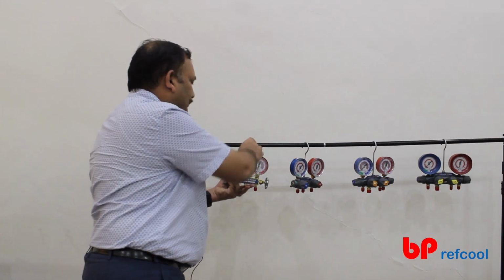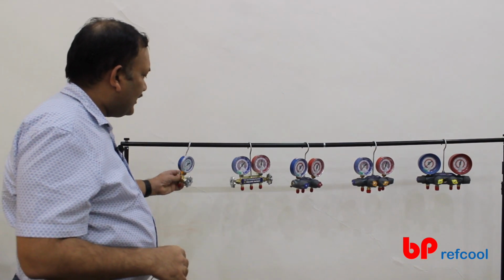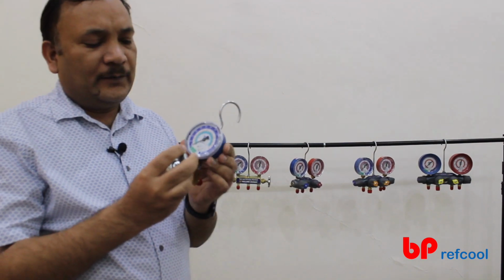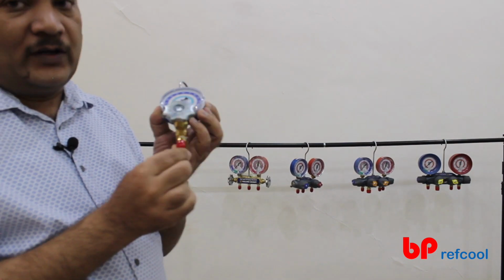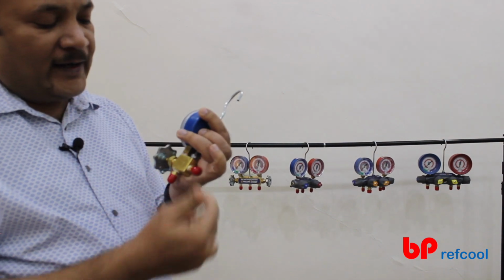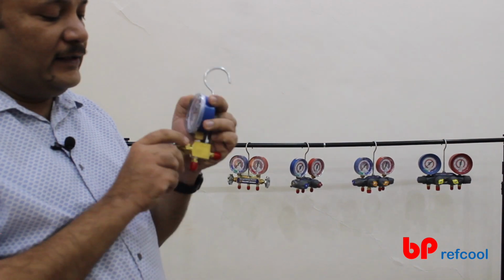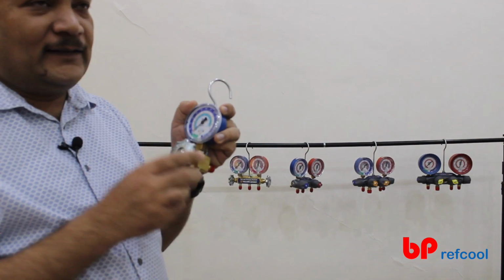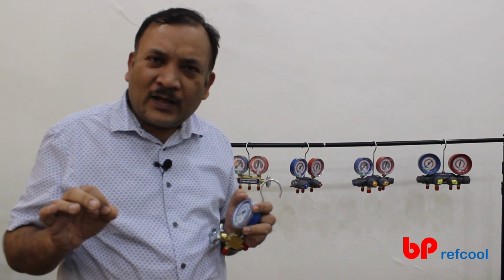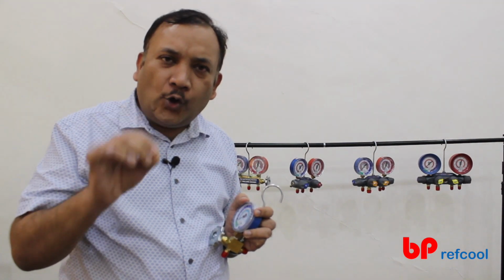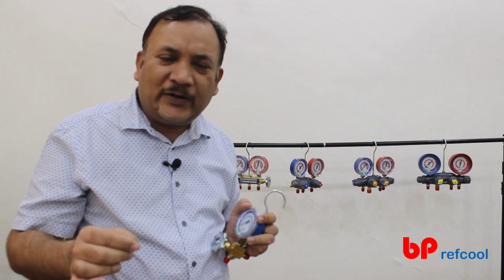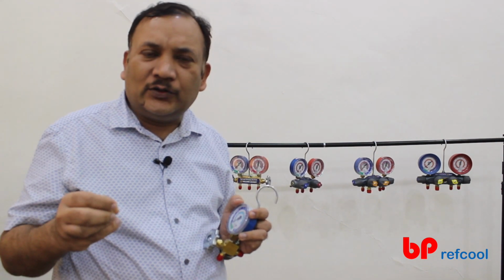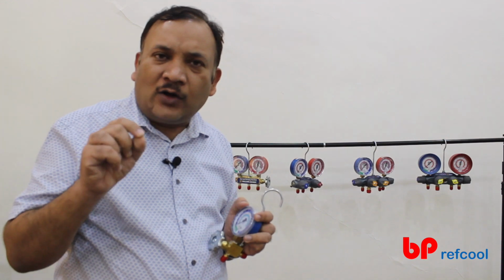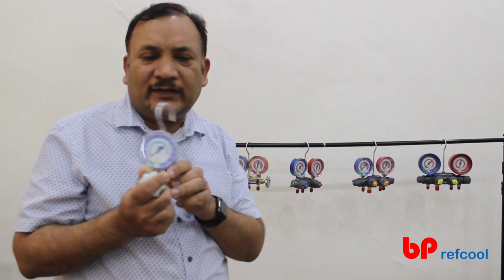Now let me give you an idea of the initial level, which is a single manifold gauge. In a single manifold gauge you have just one connection, one gauge and one back dead connection, and this valve which operates. If you are working on a system where only one port is available, such as a refrigerator, a deep freezer or a room air conditioner, then essentially you can use just a single gauge manifold, because whatever you connect is going to be connected only to the system on that one port.